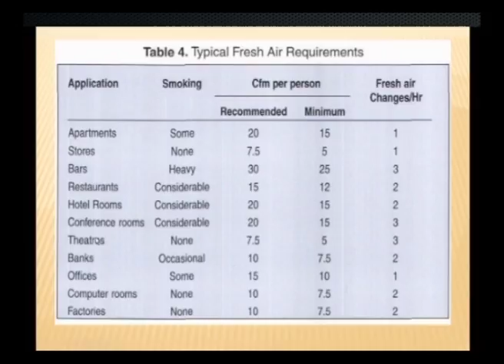The following table indicates the number of fresh air changes required and the rate at which the entire air in the system is to be circulated. Inside the hospital, an operation theatre needs 5 fresh air changes per hour, and the circulation air changes per hour is 25. So we need 25 circulation air changes per hour of the same air which is inside, and you need to give 5 fresh air changes.